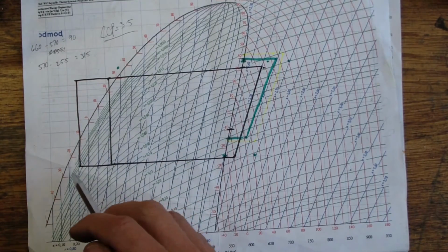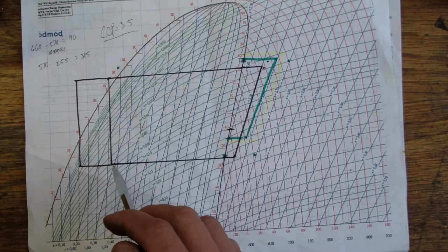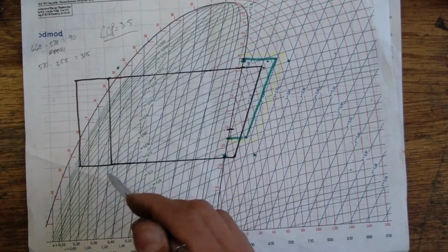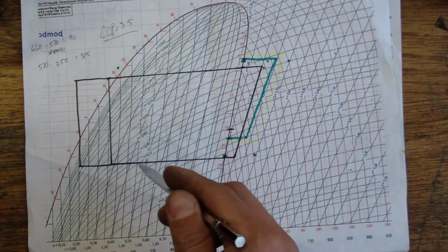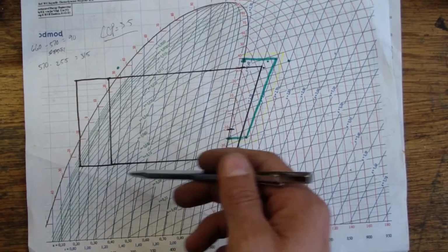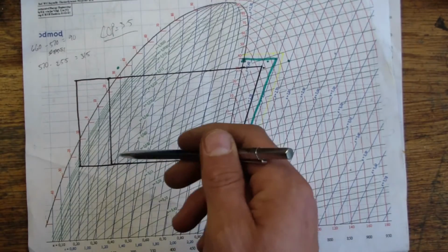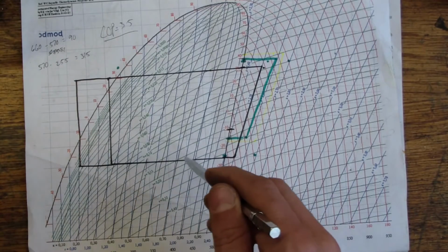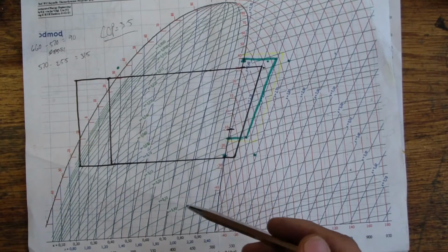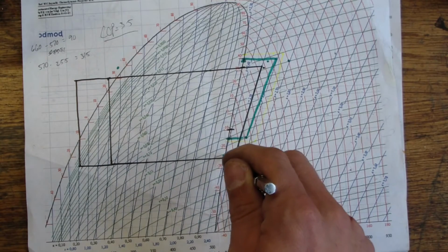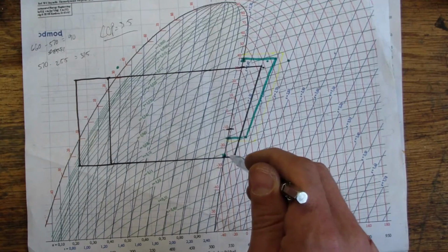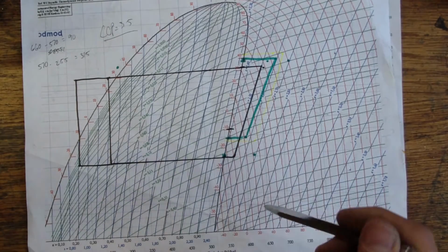So a certain portion of the refrigerant, say in this case maybe 20% or more of the refrigerant, flashes off and cools the remaining. So if we have 20% flashed off to vapor, the remaining 80% still exists as a liquid that can do cooling work. Now, of course, this evaporator should exist at a lower temperature than the heat load, so that it can absorb heat. And as that liquid evaporates and absorbs heat, it's going to increase in enthalpy. And we're going to travel across the chart again, increasing in enthalpy the whole time, absorbing heat from the environment, lowering the temperature of the environment, until we get back to the saturated vapor line. At which point we cross the saturated vapor line, we're in the suction line, and we're going to end up as a more rarefied gas, increasing temperature and crossing these isothermals again.